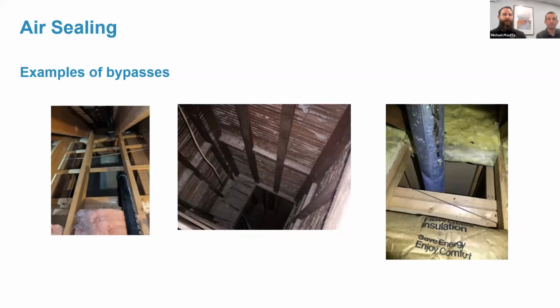In kind, those should be addressed during the air sealing phase, because it should be checked that the dampers and louvers are set correctly in the mechanical ventilation, bringing in only the required amount of outdoor air. But I think that's a topic for a different discussion. But on the smaller facilities, in order to ensure that, if no mechanical ventilation is being done in the building, the blower door testing pre and after the air sealing is performed is the best means of ensuring that the building hasn't been oversealed. So I hope that answers your question. If not, please let me know. I'd be happy to go into it further.